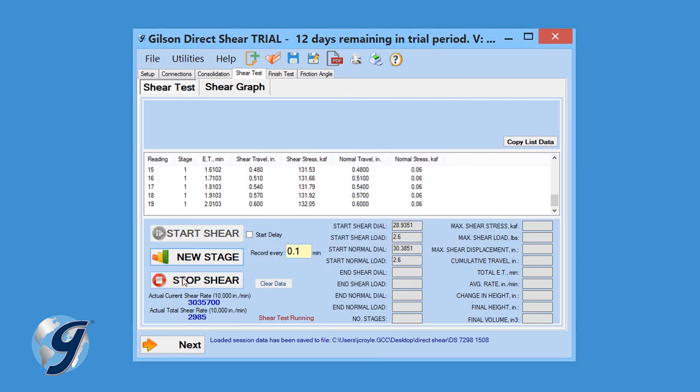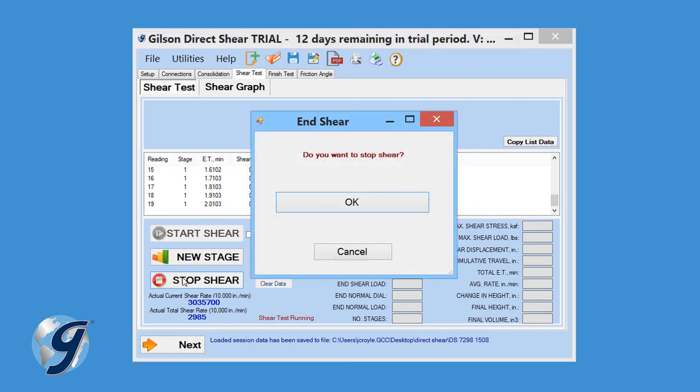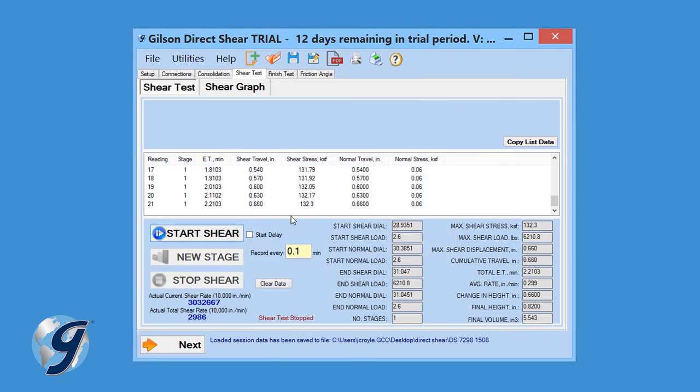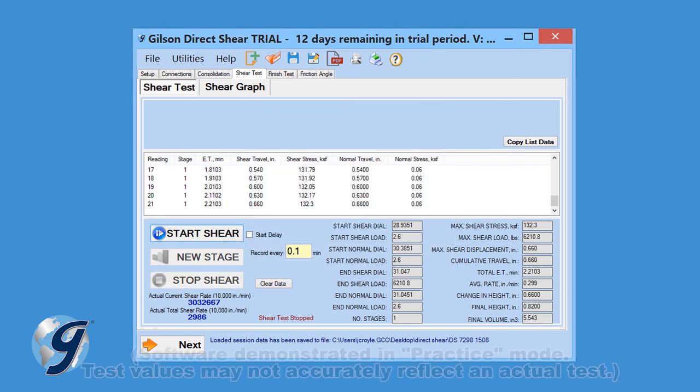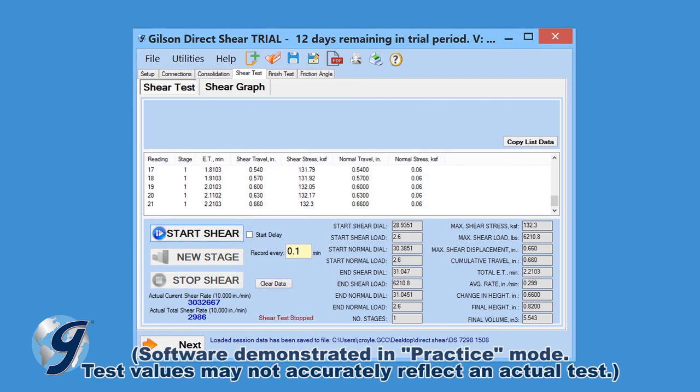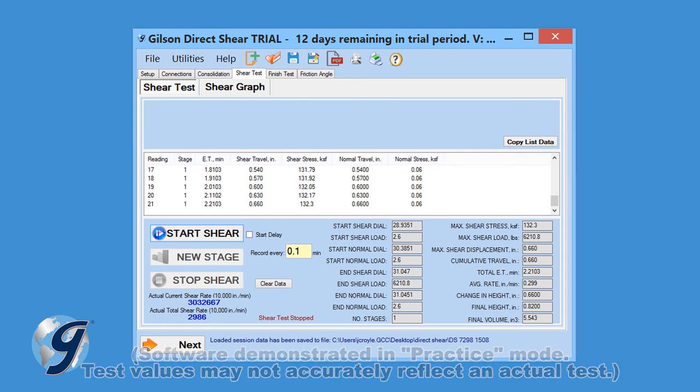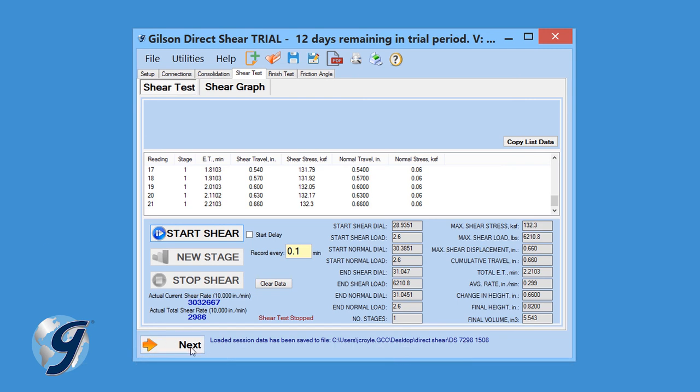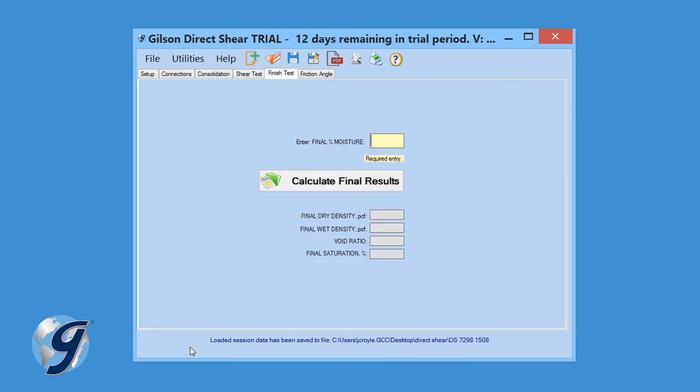Once completed, click Stop Shear to stop collecting test data. When asked, do you want to stop shear, click OK to stop the shear test. Calculations are then performed and will appear in the bottom half of the Shear Test tab. Click Next to continue to the Finish Test tab.